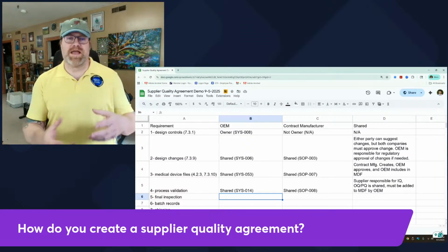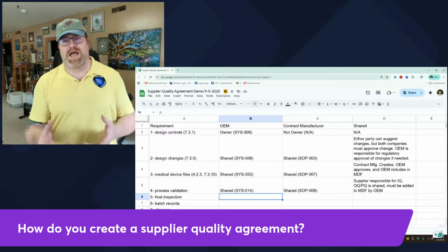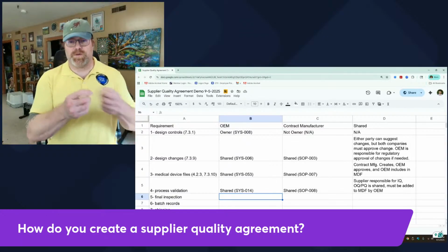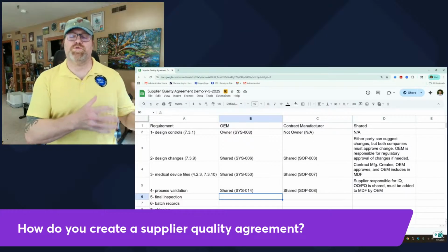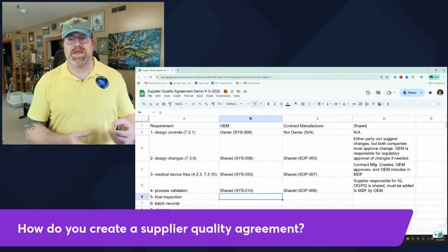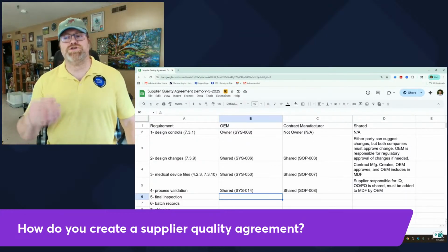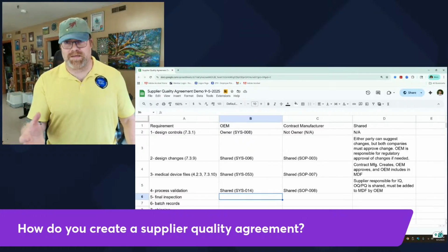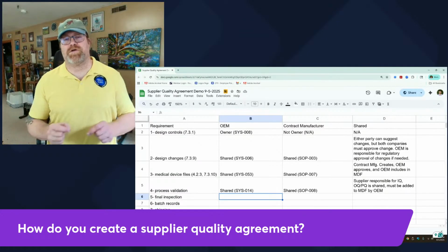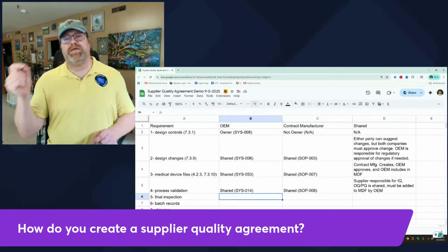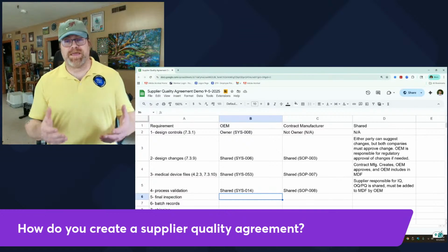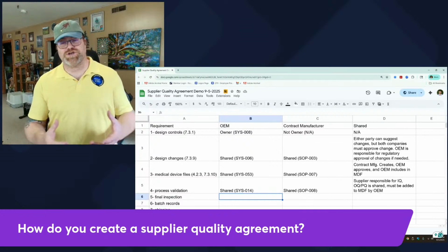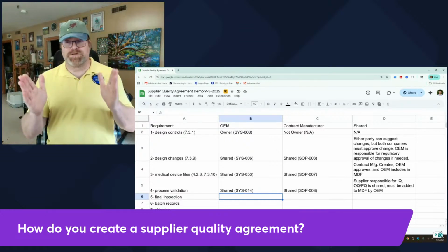And you can use that to create your dimensions and your tolerances for your drawings. So you make some prototype parts and you figure out what the standard variation is in these parts, and then you incorporate that information into the drawings. And if you're trying to do some validation, during the OQ process, the OQ is when you find out what the variability of the process is before you write your acceptance criteria for the PQ. Because the PQ is going to be done at the nominal conditions, and you got to be within your acceptance criteria.